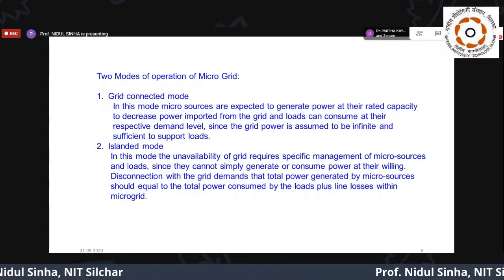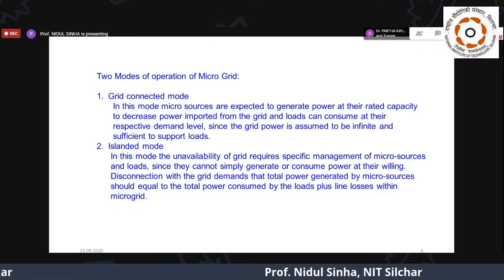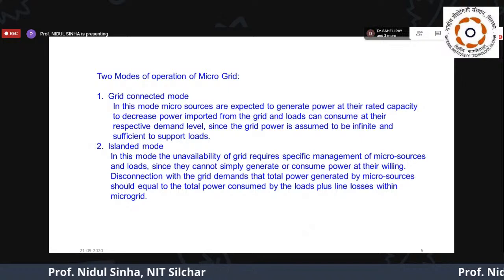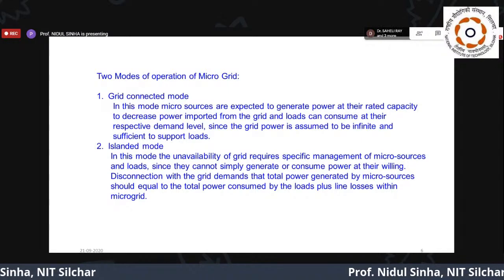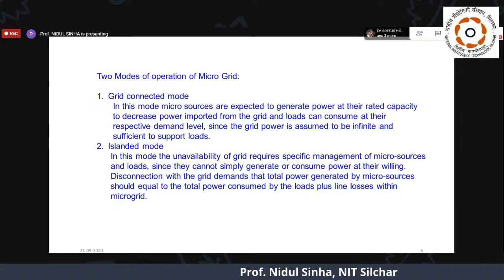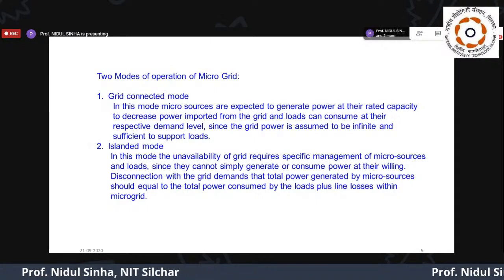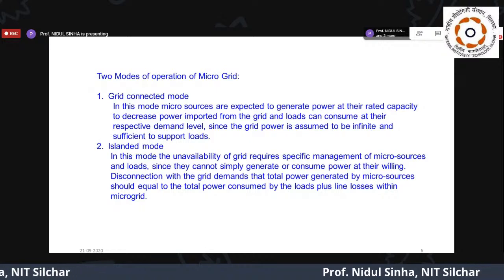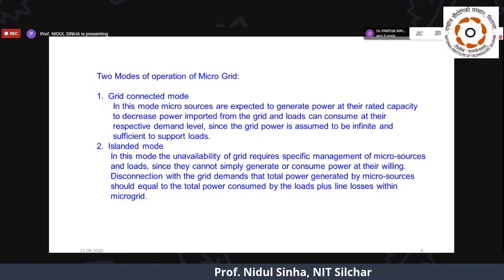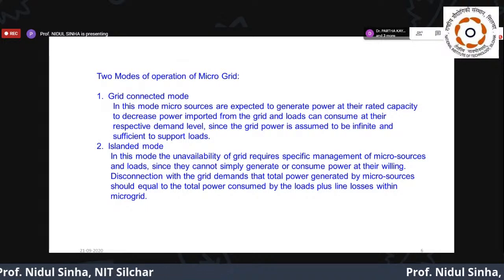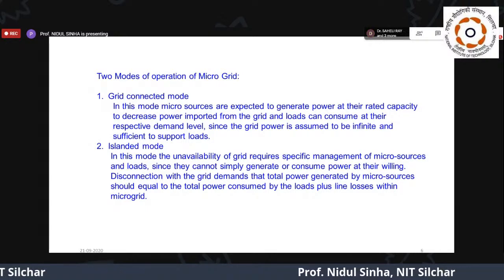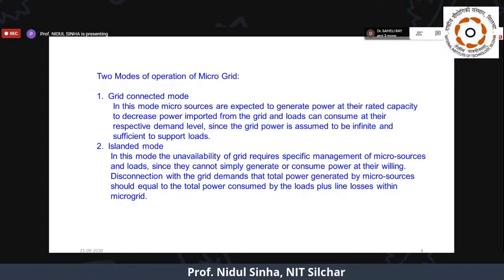In a conventional system we go for the large grid. There are some constraints considered which do not allow going for 60 Hz, for example in developing or underdeveloped countries. But that's not prevalent when we talk about an islanded system. If it's independently islanded, I'm talking about AC microgrid. If you go for a DC microgrid, nothing doing - there's no frequency at all.